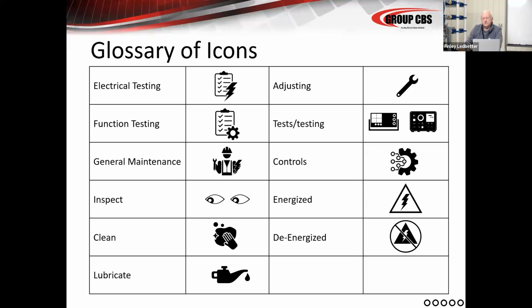That's what you're asking your lubrication to do. And lubrication is one of the real keys here, because lubrication, time, heat, chemical reaction, airborne contaminants are all the nemesis of lubrication. So quite often you'll see interrupting times and parting times that will go up proportionally with time. So there's been studies done over what the correct maintenance cycle might be. And for the purpose of this presentation, I've selected 5 years. I personally don't believe in 5 years for all applications. I think 3 is kind of a sweet spot.